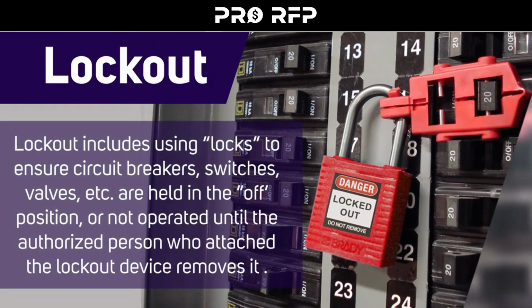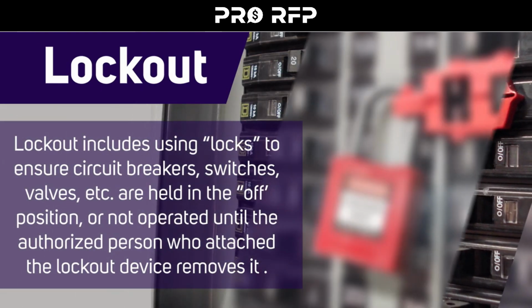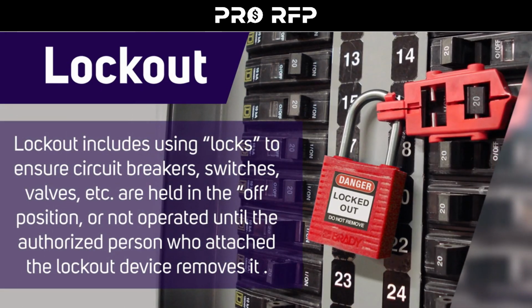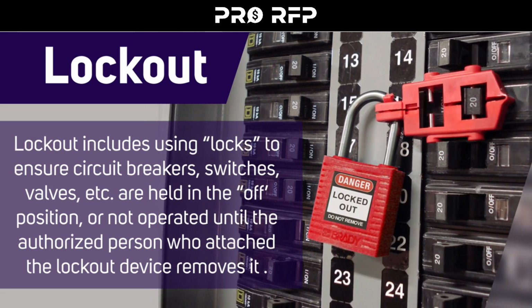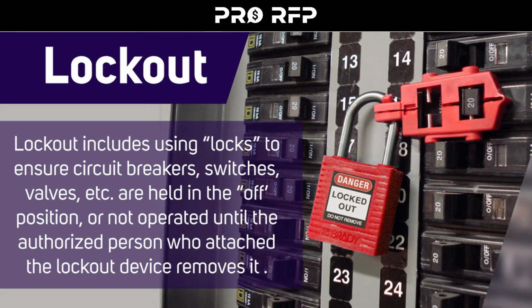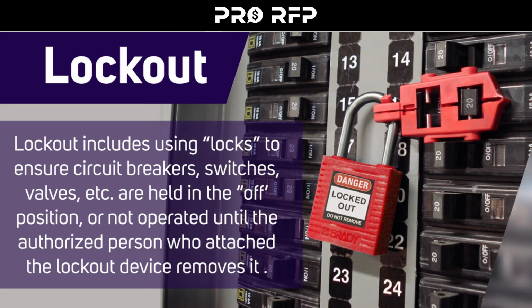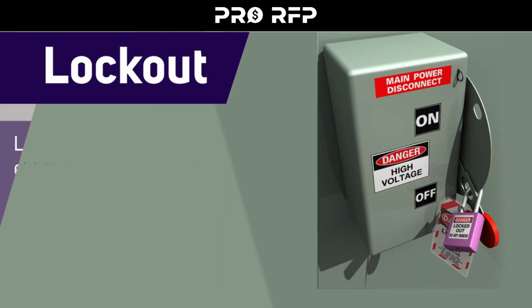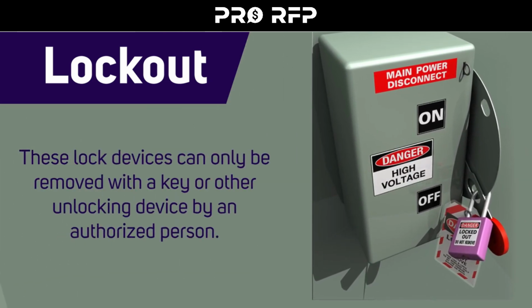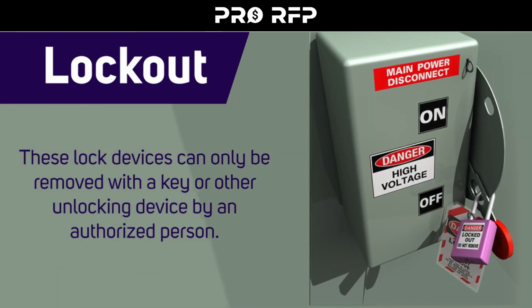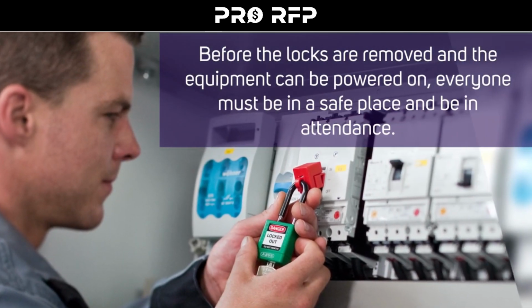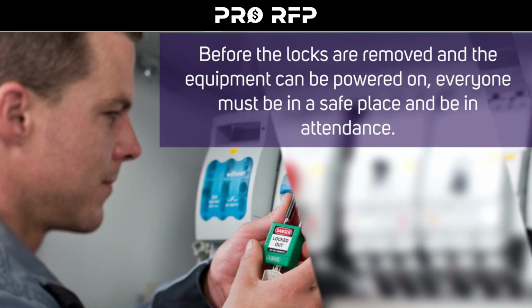Lockout includes using locks to ensure circuit breakers, switches, valves, etc. are held in the off position or not operated until the authorized person who attached the device removes it. These lock devices can only be removed with a key or other unlocking device by an authorized person. Before the locks are removed and the equipment can be powered on, everyone must be in a safe place and in attendance.